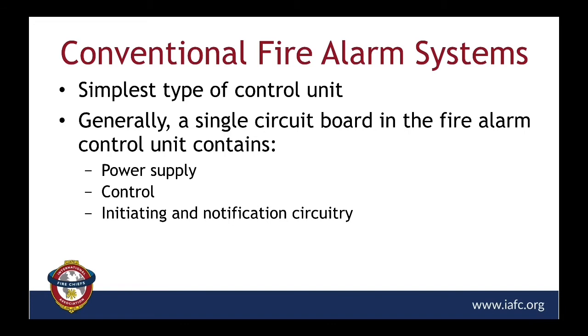So let's talk about the conventional fire alarm system. You're going to find that this is the one that's been around the longest. These panels have birth dates going back into the 1950s, maybe even a little bit sooner. It's the simplest type of control unit. In today's world of code advancements, the code is actually limiting where a conventional fire alarm system is used. They have a place and a location in our buildings, but you're going to find them primarily in smaller systems, smaller buildings, and very frequently in buildings where we're just monitoring the fire sprinkler system. But they do have the same components that Richard was talking about: power supply, a main control unit, and initiating and notification circuitry.